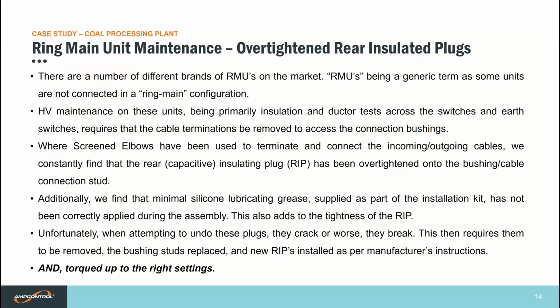Unfortunately, when attempting to undo these plugs, they crack, or in the worst scenario, they break. This then requires them to be removed, the bushing studs replaced, and the new RIPs installed as per manufacturer's instructions. Just to sidetrack a little, as this situation is common during high voltage maintenance on sites, we have developed a procedure to replace the broken rear insulating plugs. If it's found on site and we attempt to undo the plugs, or if there's several plugs, after discussion with the customer, we may be able to replace the faulty plugs depending on the brand and if we have spares for that brand of RIP. If not, we will need to obtain replacement parts and return at a mutually suitable time to complete the repairs.